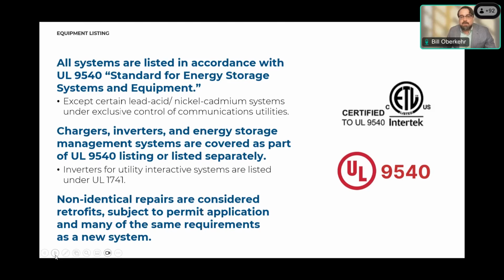The point of the UL 9540 field listing goes to this third bullet here of non-identical repairs and retrofits. A field listing is something whereby if we have a system already in the field and one of the subcomponents is recalled or needs to be replaced with a non-identical piece of equipment, the 9540 field listing can be used as a supplement. We can't take all this equipment back to the lab and recertify it, so we have folks recertify this project in the field because there's this one minor repair taking place. That's helpful to understand at the highest level, the difference between the two.